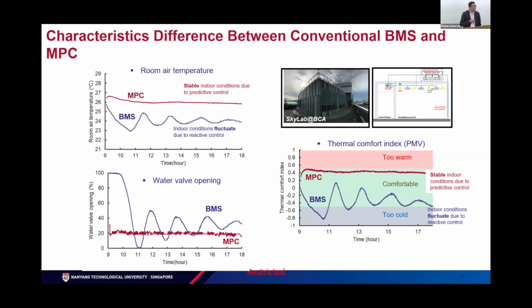So as you can see from the first figure, which is the variation of room temperature for a typical day in one of our test cases, when we have employed the PID for BMS, we are seeing a very fluctuating temperature within the room. But when we do MPC, due to our forward prediction of various disturbances coming into the building, we're able to maintain the condition in a very steady manner.